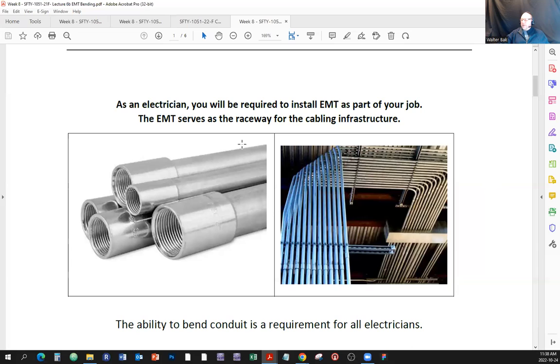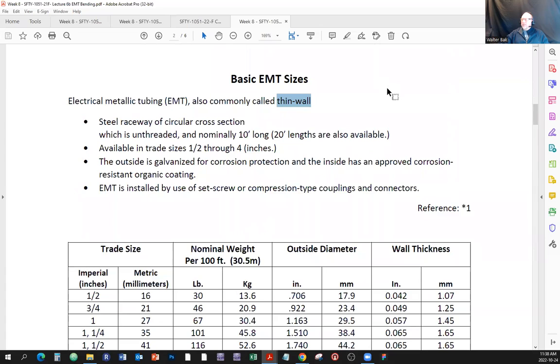The ability to bend conduit is a requirement for all electricians. Basic EMT sizes — electrical metallic tubing is also commonly called thin-wall. When you hear 'thin-wall,' that's basically EMT. It was named thin-wall because of the thickness of this wall. EMT is a steel raceway of circular cross section which is unthreaded. Rigid metal conduit — you put a thread on the end of it. EMT normally comes in 10-foot sections, sometimes 20-foot lengths, but 10-foot sections are the most common because they're easier to transport.